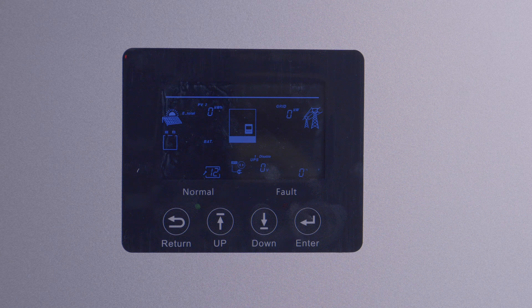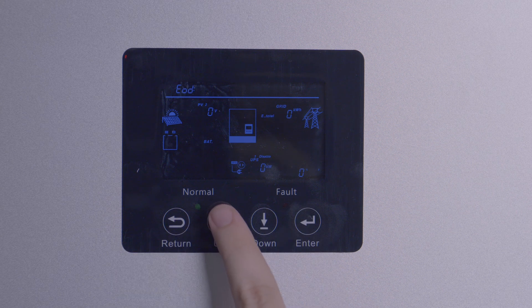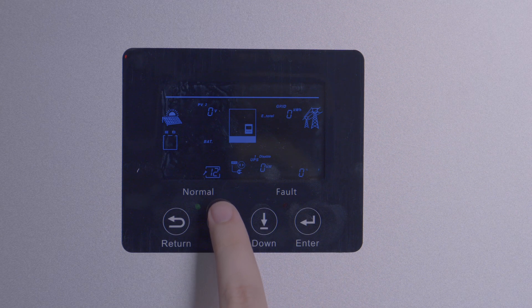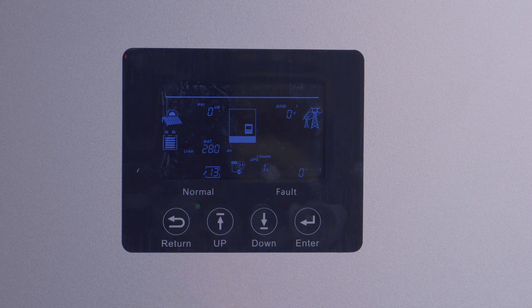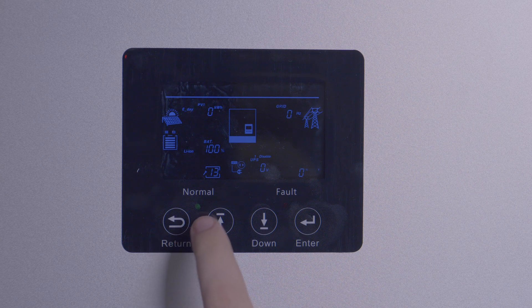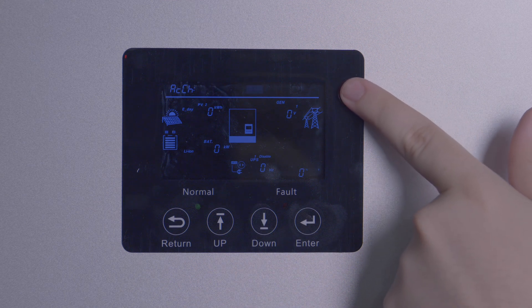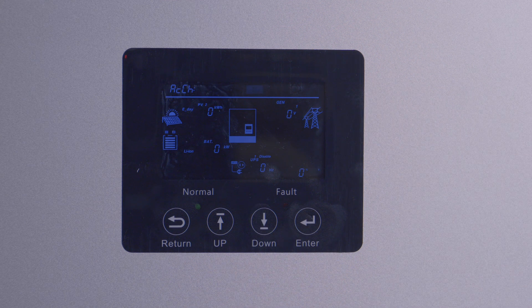If there are no other options, the inverter will simply stop outputting power until PV, generator, or grid is present. Setting thirteen is for AC voltage range, with APL for a lenient voltage window and UPS for a tight voltage window. Setting fourteen is AC charge setup, where you can input a start and stop battery charge value and a specific time of day — useful if you have a time-of-use plan with free power nights or weekends.